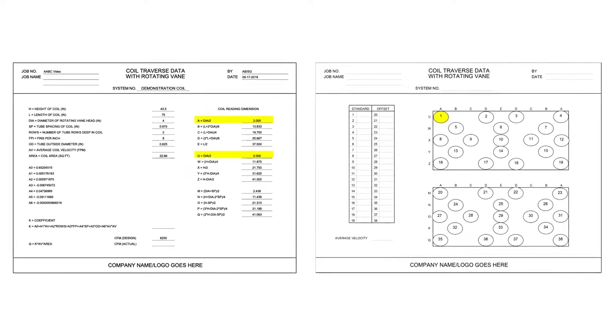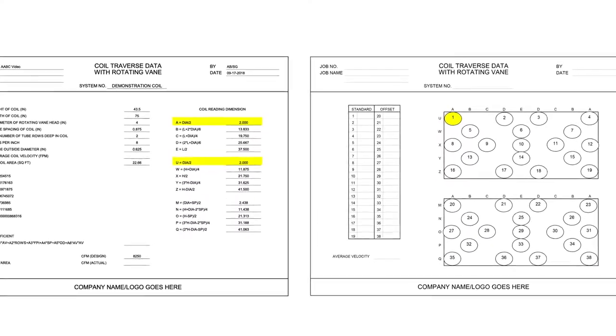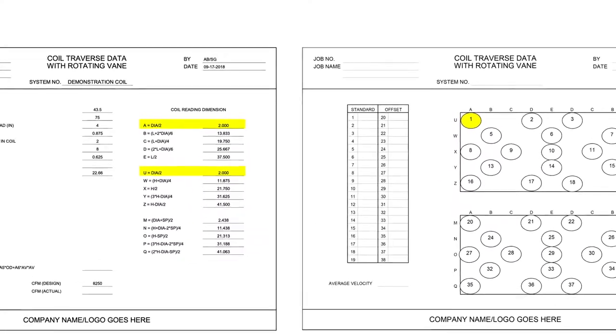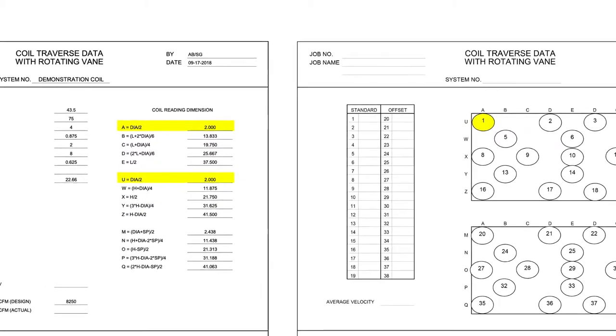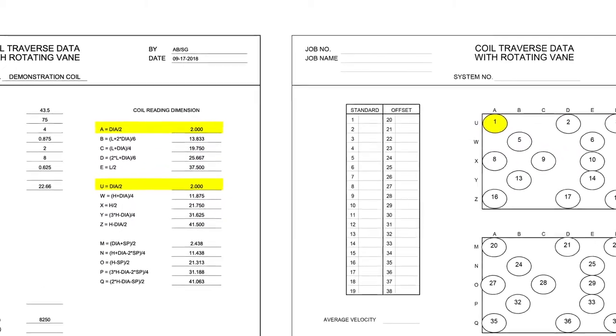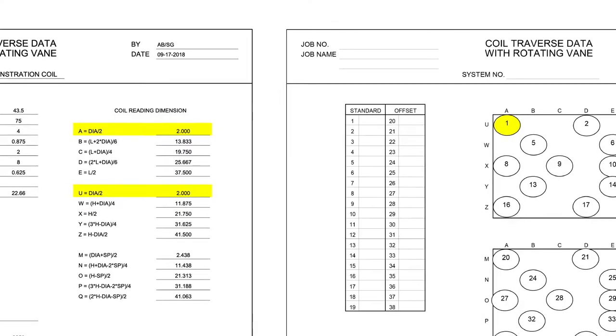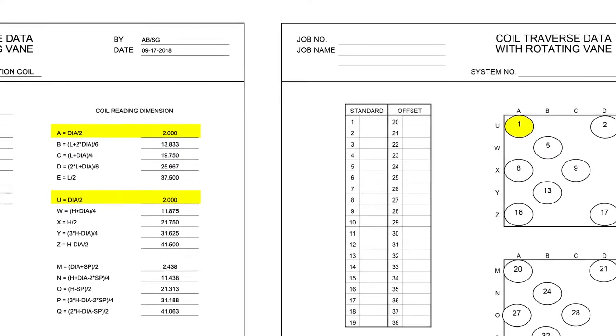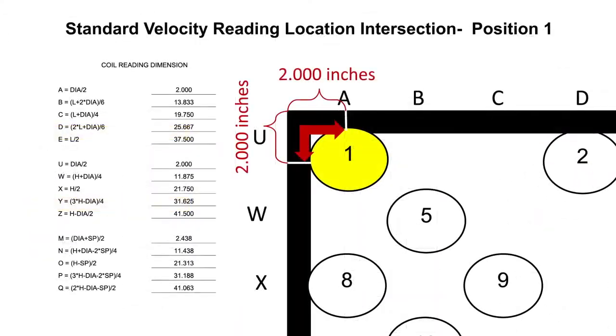Position 1 is located in the top left at the intersection of A and U. The value for A equals the diameter of rotating vane head divided by 2, and the value for U equals the diameter of rotating vane head divided by 2. The standard velocity reading location for position 1 is at the intersection of A equals 2 inches and U equals 2 inches.